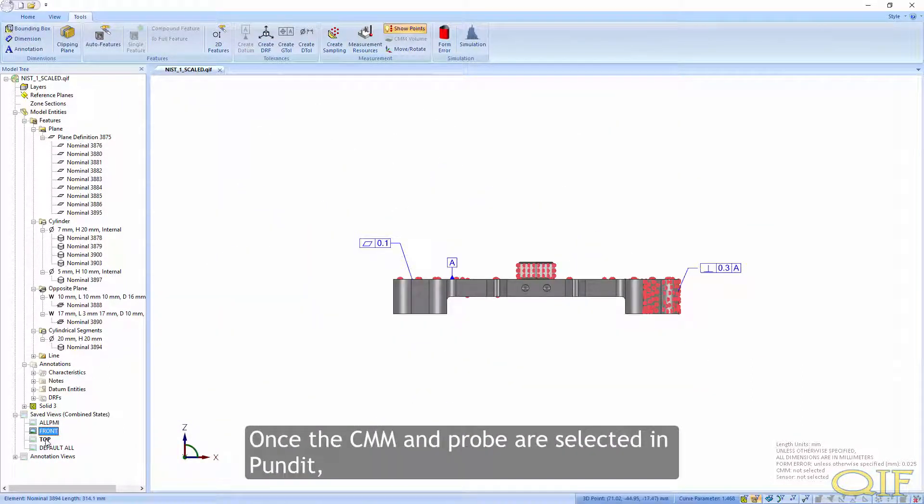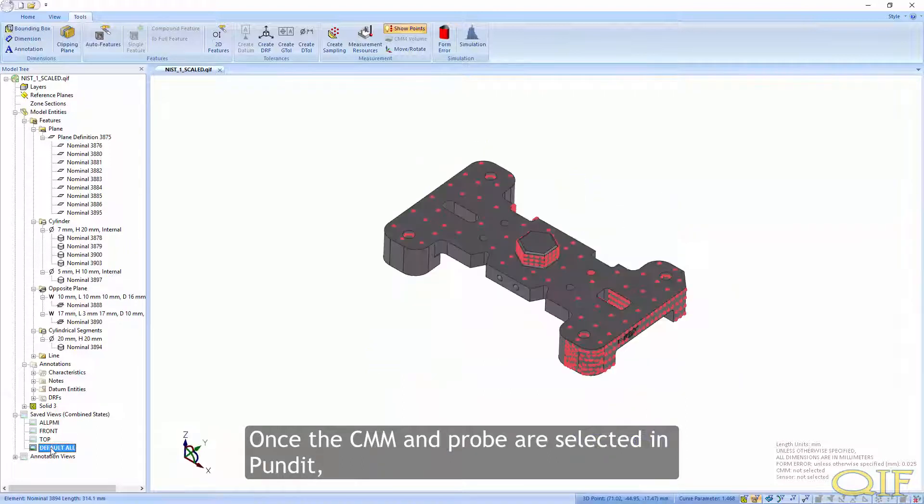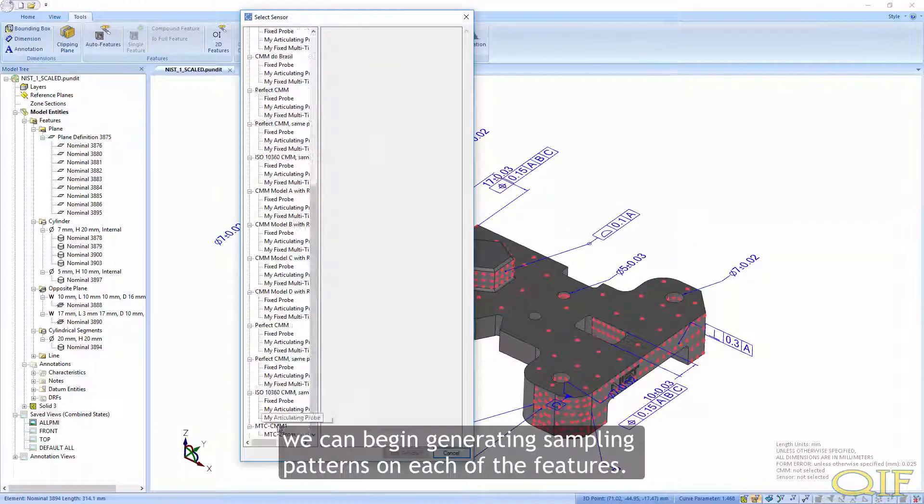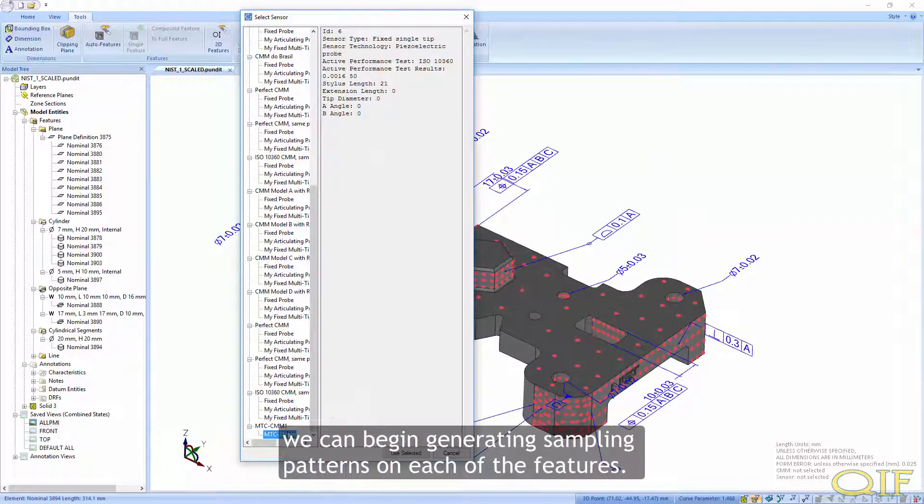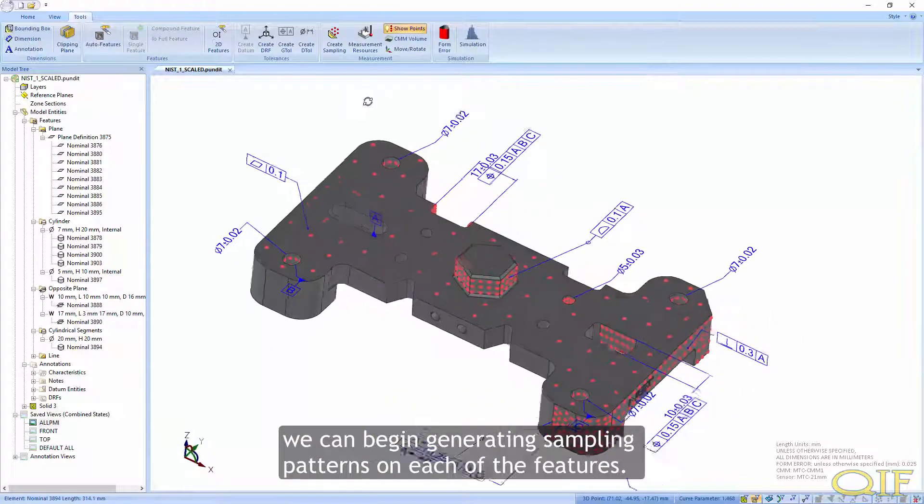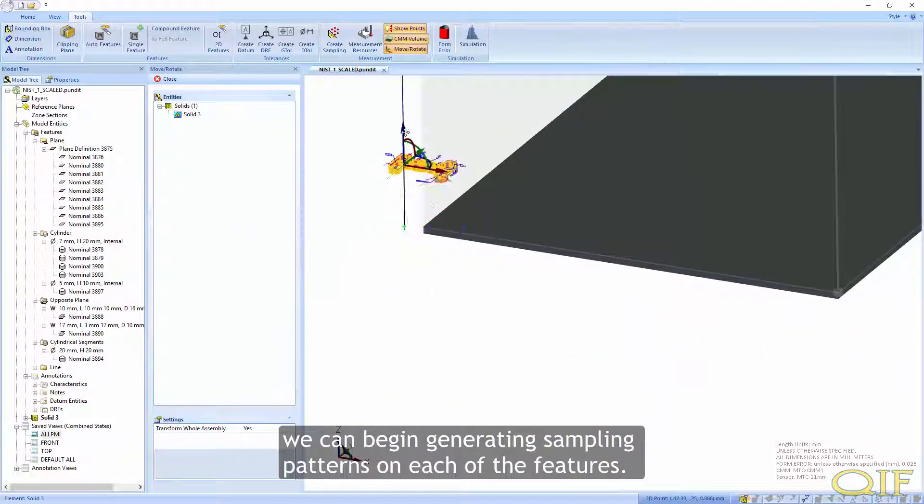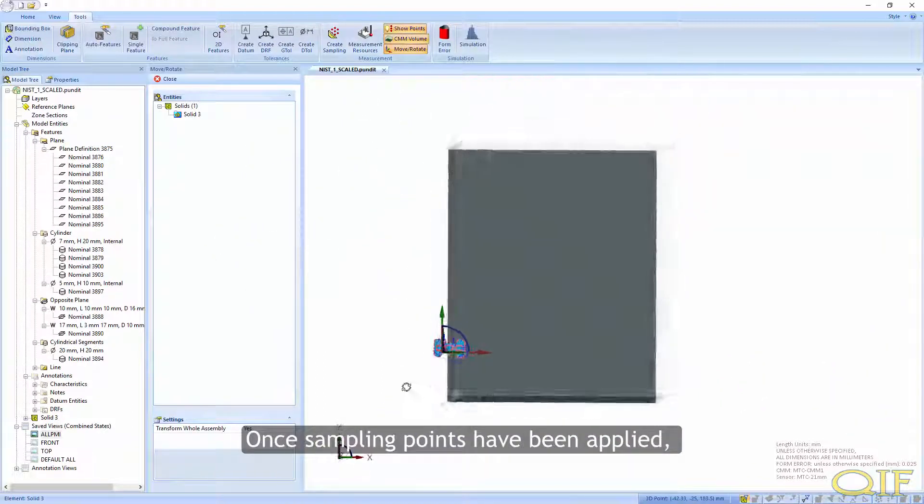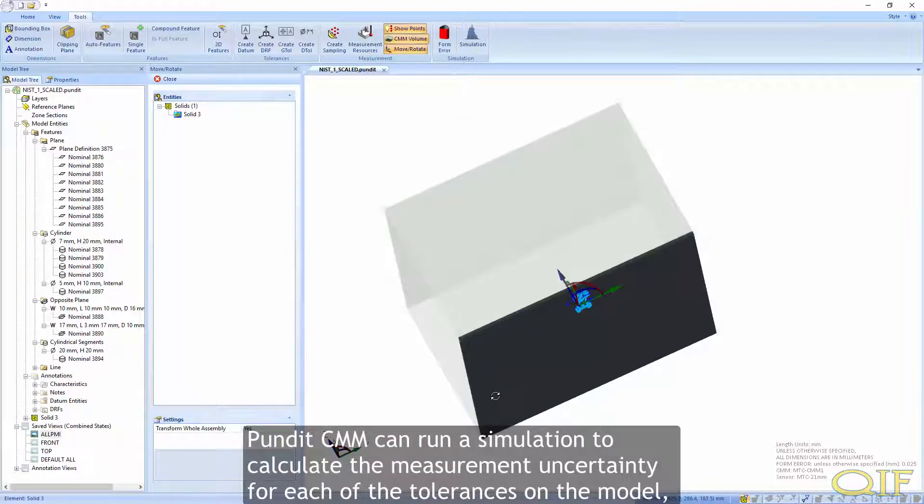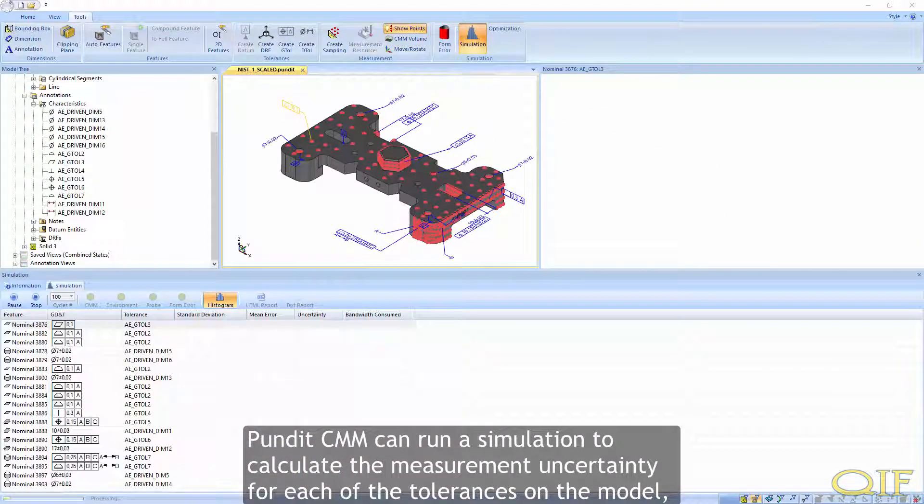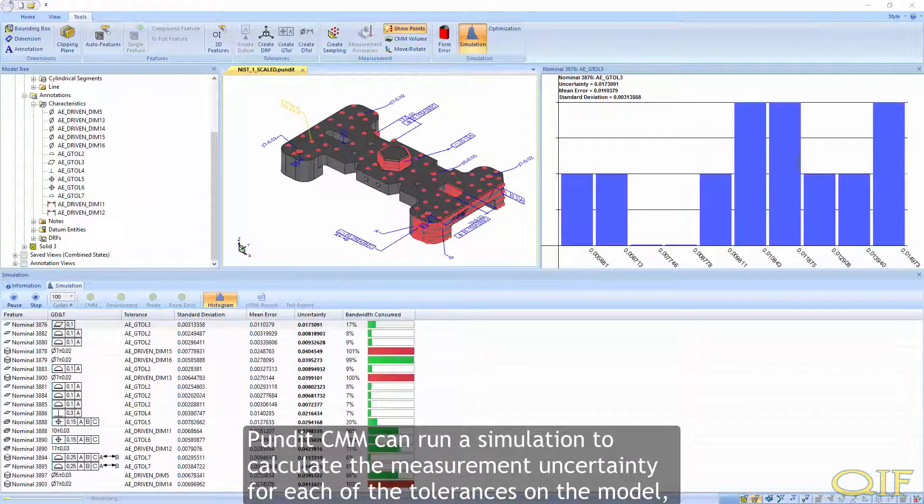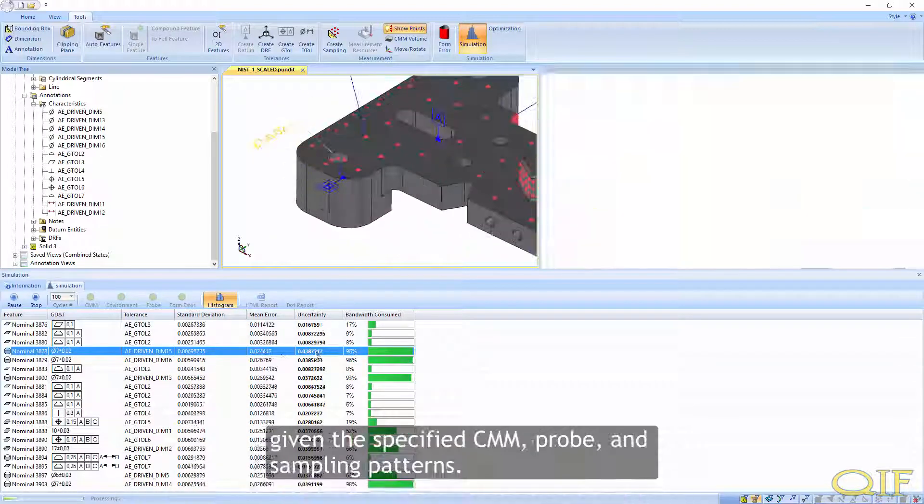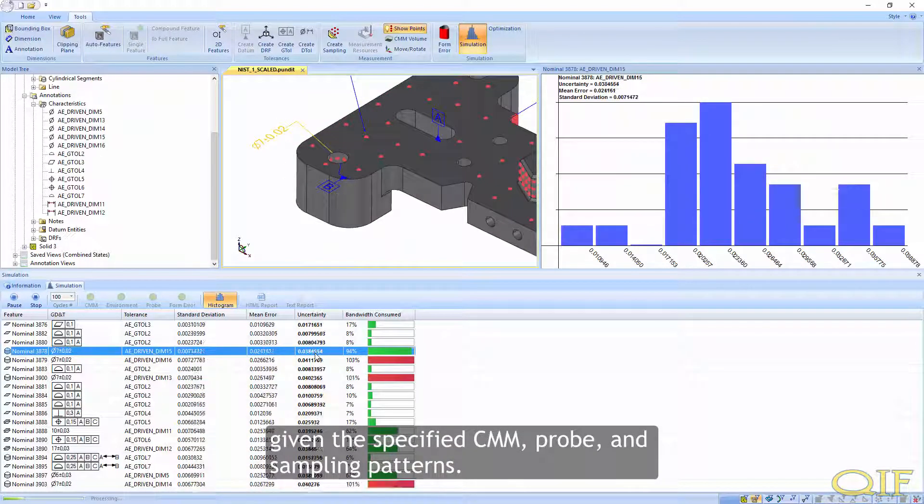Once the CMM and probes are selected in Pundit, we can begin generating sampling patterns on each of the features. Once sampling points have been applied, PunditCMM can run a simulation to calculate the measurement uncertainty for each of the tolerances on the model, given the specified CMM, probe, and sampling patterns.